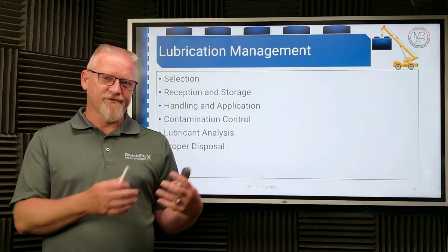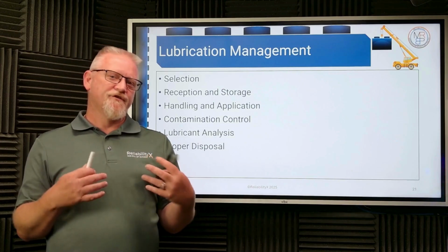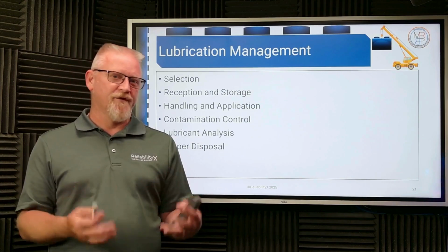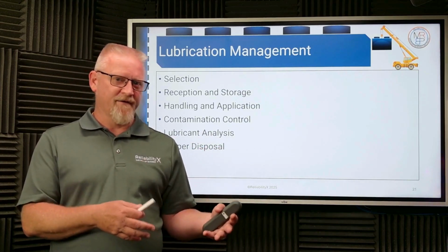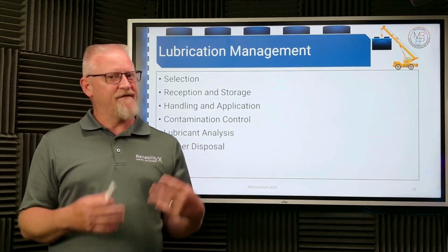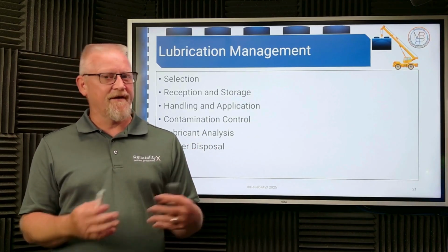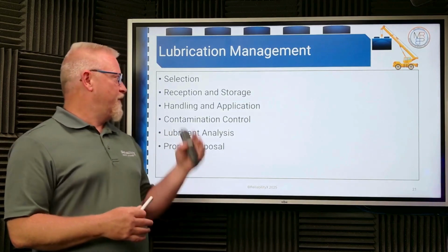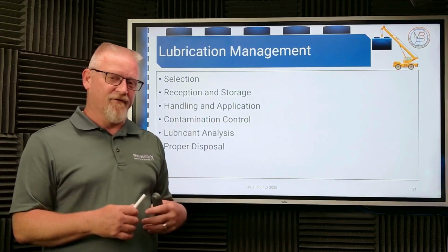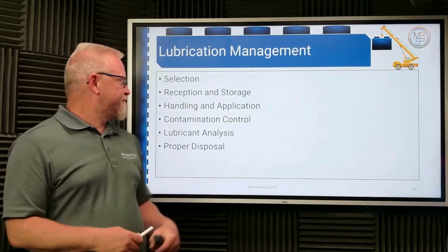The particles inside your lubricants should be smaller than the space allowed for your film thickness of your bearing, or clearances in between things like roller elements and the inner and outer race. And so we want to make sure that we are receiving that lubricant and filtering it appropriately.